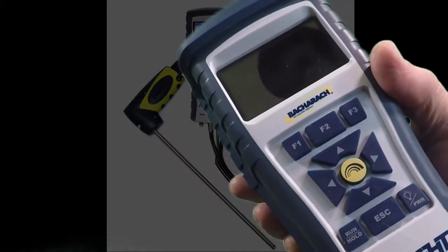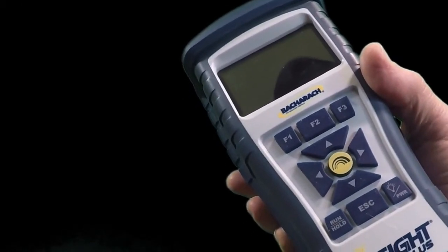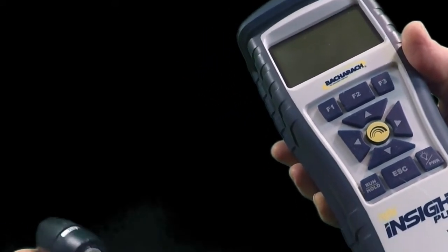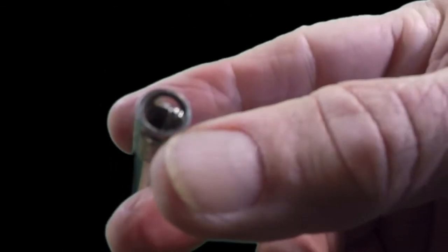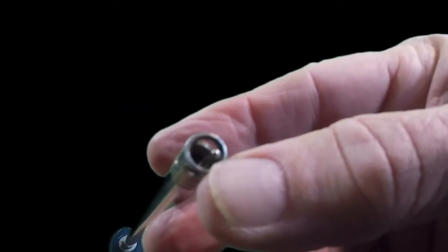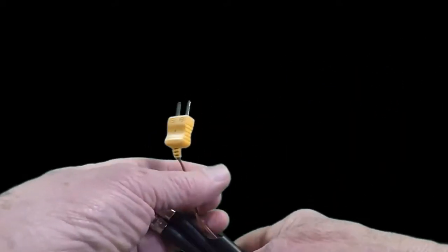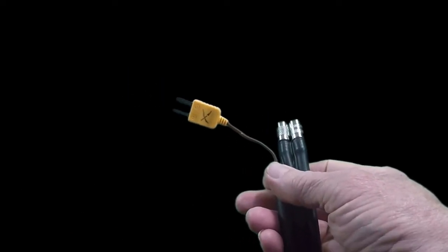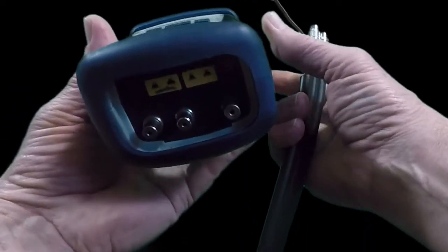This is the Insight Plus. First thing we'll do is plug in the hose and probe assembly. If you look at the end of the probe, you'll see a small metal rod sticking out of the end. That is the thermocouple that measures stack temperature. The other end of the hose assembly has a K-type thermocouple plug. That's going to go into the bottom of the instrument.